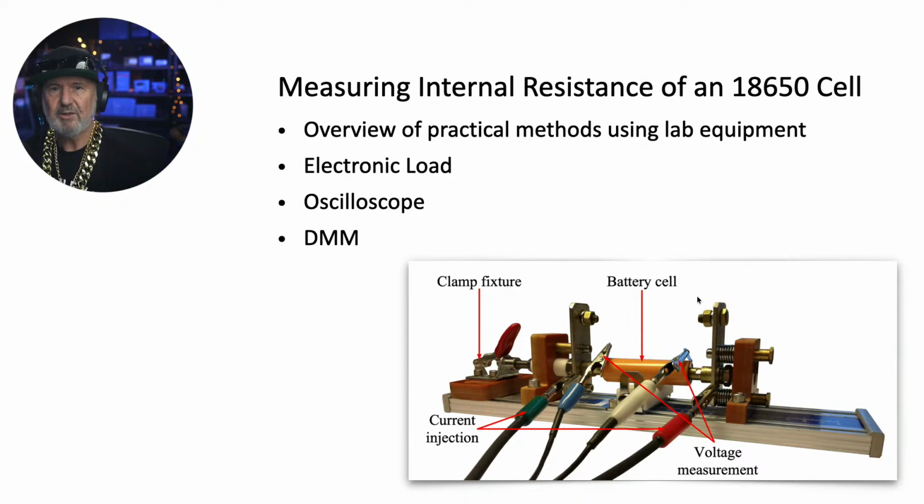And you do need to apply a load for most of the tests. You can use an oscilloscope, which gives you the most accurate results, or a digital multimeter. So as you can see straight away, this is not something for you to do on site when you're installing a system. This is something the manufacturer would do in a lab to calculate the fault current.